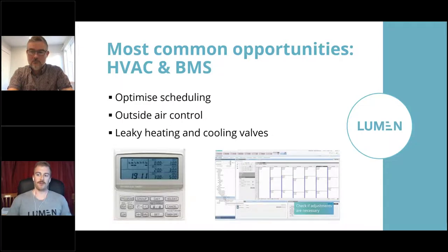The number one thing we always find is that some equipment is operating when it's not required. So we recommend that you're regularly checking your schedules to make sure they are matching the actual requirements. This can be done on local controllers like the heat pump controller on the left there, or through your building management system on the computer in the image on the right there.